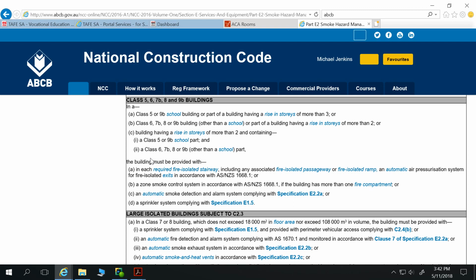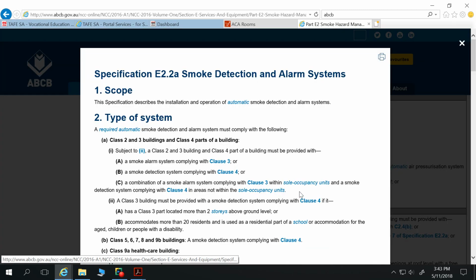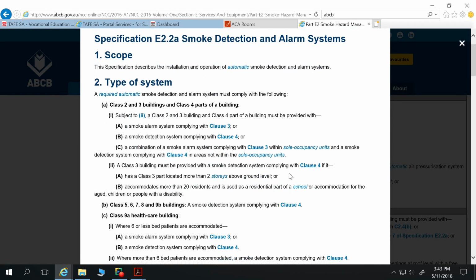And you can have a look at AS/NZS 1668.1 and explore those options. Well, let's look at this automatic smoke detection and alarm system complying with specification E2.2A. That's what I'm suggesting. So, smoke detection and alarm systems. Type of system: required automatic smoke detection and alarm system must comply with the following. For class.